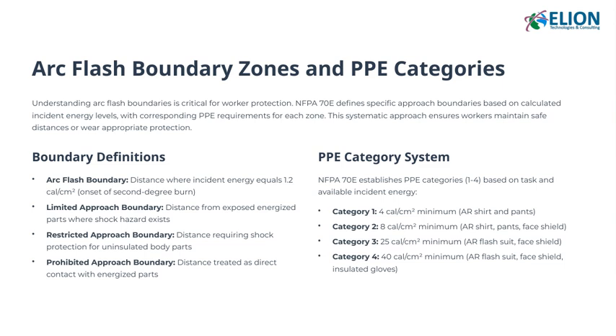Next, we have the limited approach boundary. This is the distance from exposed, energized parts where a shock hazard exists. It's a safety zone that helps prevent accidental contact with live parts. Then there's the restricted approach boundary. This is even closer to the energized parts and requires shock protection for uninsulated parts of the body. Only trained and properly protected personnel should enter this zone. And finally, the prohibited approach boundary. This is considered a no-go zone. It's treated as direct contact with energized parts, and only qualified personnel with the right PPE should go there.